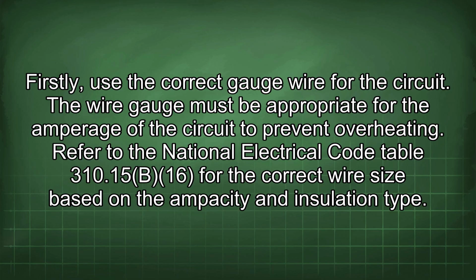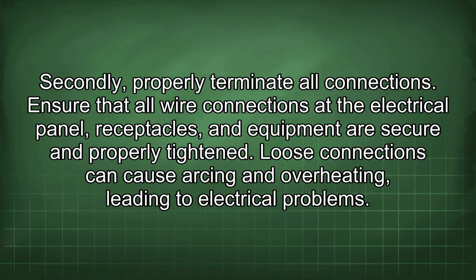Firstly, use the correct gauge wire for the circuit. The wire gauge must be appropriate for the amperage of the circuit to prevent overheating. Refer to the National Electrical Code Table 310.15(B)(16) for the correct wire size based on the ampacity and insulation type. Secondly, properly terminate all connections. Ensure that all wire connections at the electrical panel, receptacles, and equipment are secure and properly tightened. Loose connections can cause arcing and overheating, leading to electrical problems.